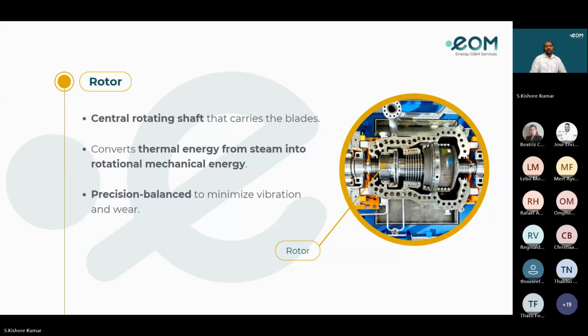Rotor. The rotor is a rotating component with multiple blades attached to the shaft, extracting energy from high pressure steam and converting it into mechanical energy. The rotor is a long, high-strength shaft that runs through the center of the turbine. It carries the moving, rotating blades and is supported by bearings at both ends. As steam passes over the blades, it causes the rotor to spin at high speeds, usually 3000 RPM or more, depending upon the frequency of the system.